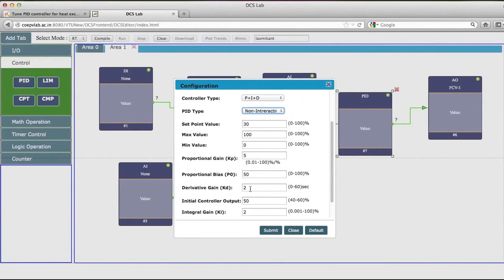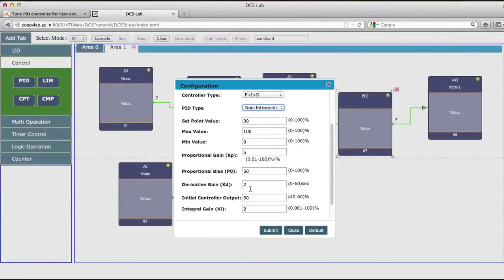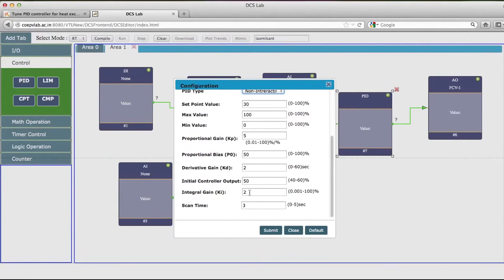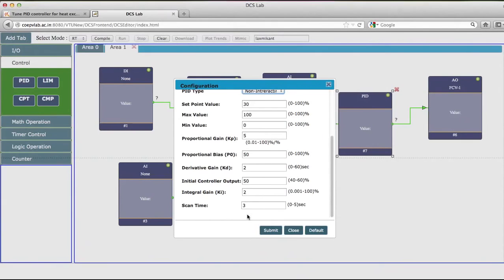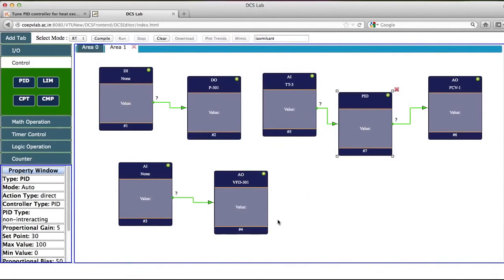The bias I have kept at 50. Derivative gain is kept at 2. The initial controller output is 50. Integral gain is 2. And the scan time is 3, which means every after 3 seconds your PID controller will calculate the values. I will submit this indicating that the PID controller is configured.